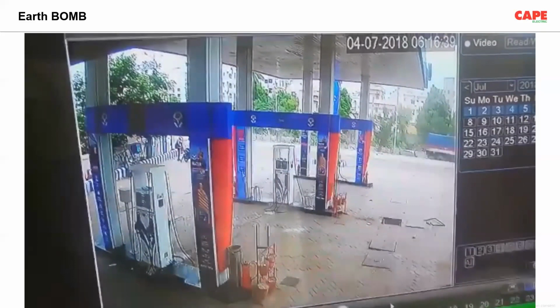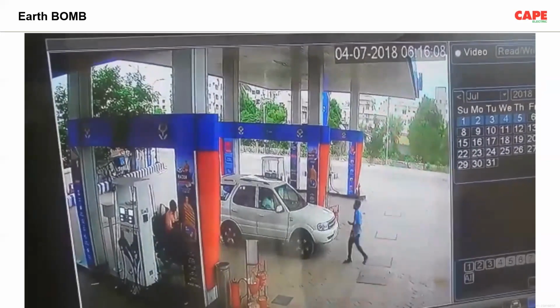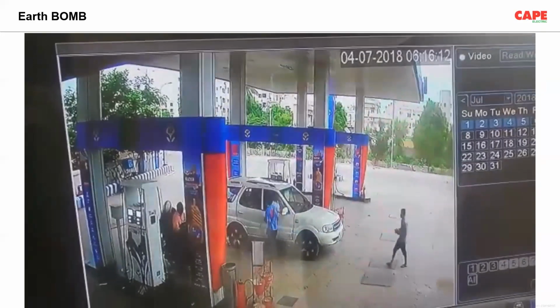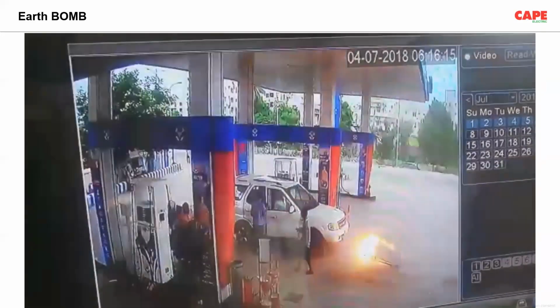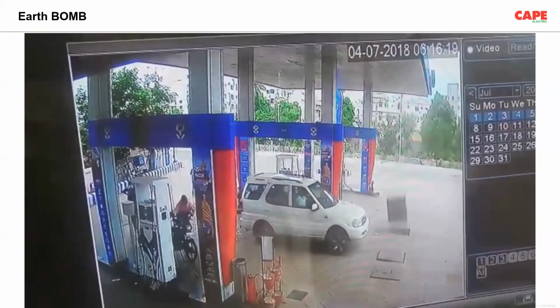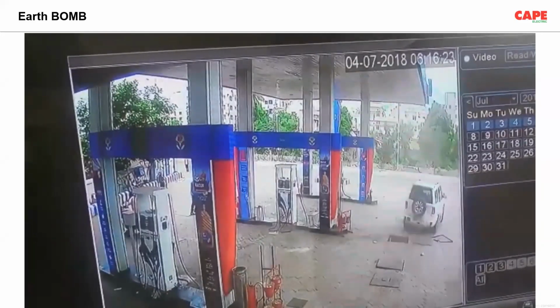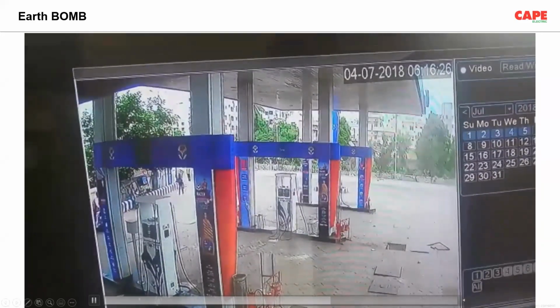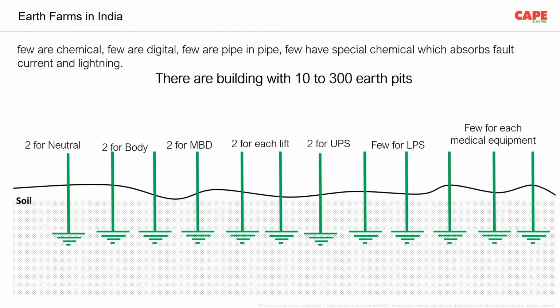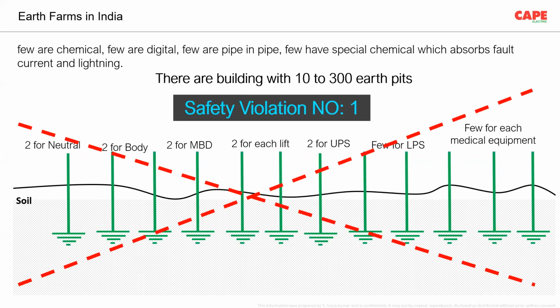But the way we are following electrical safety in our buildings, even if this kind of earth bomb happens, you don't need to be surprised, because each part of the building is connected to a separate earth electrode. Then the joints are corroded, and such explosions happen. If somebody asks whether explosions are possible, I would say yes, of course. But I don't know whether this case is due to that kind of earth electrode. So the first evil against electrical safety in India is the story called two for neutral, two for body. This is the first safety violation. I repeat it every time in my presentation because it is the most important violation happening in India.